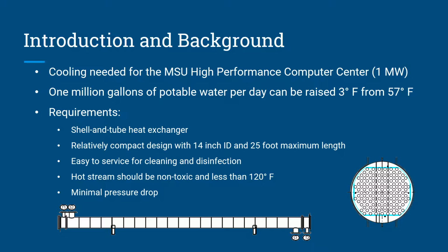The MSU Office of Infrastructure Planning and Facilities has determined that the MSU High Performance Computing Center will need 1 megawatt of cooling. They have determined that there are 1 million gallons of potable water per day that can be used in the feed water system, and that the water can increase 3 degrees Fahrenheit from its inlet temperature of 57 degrees Fahrenheit.